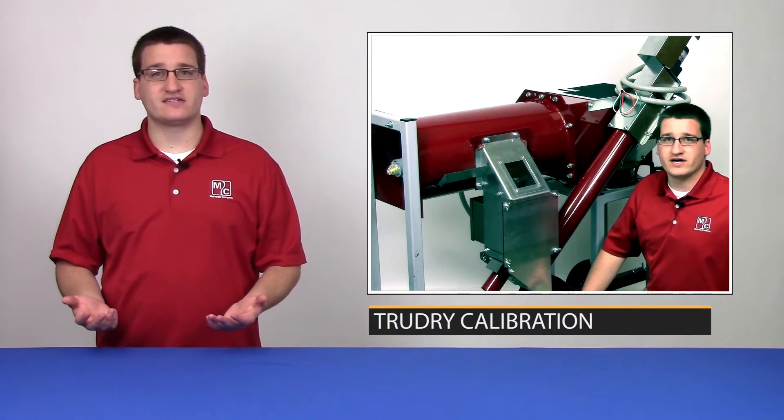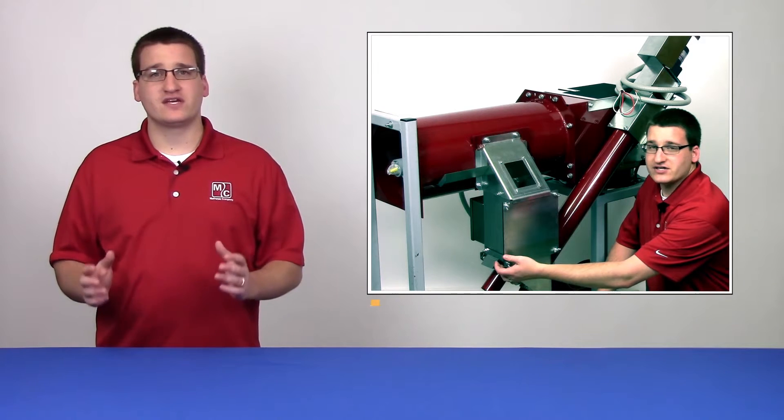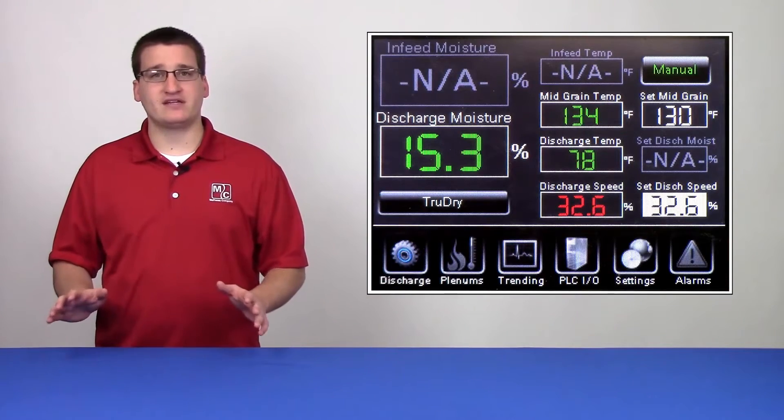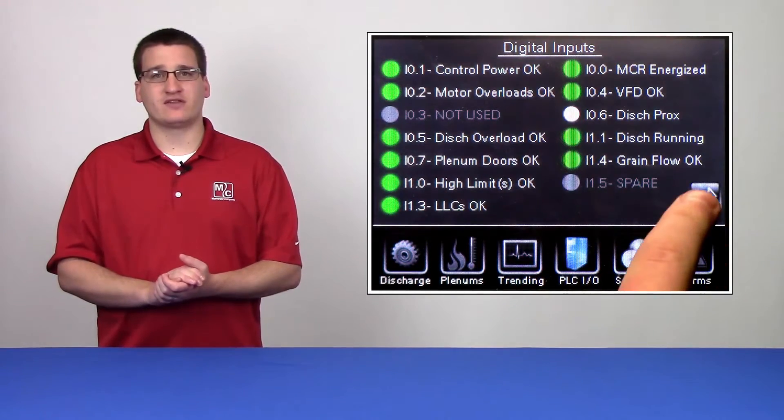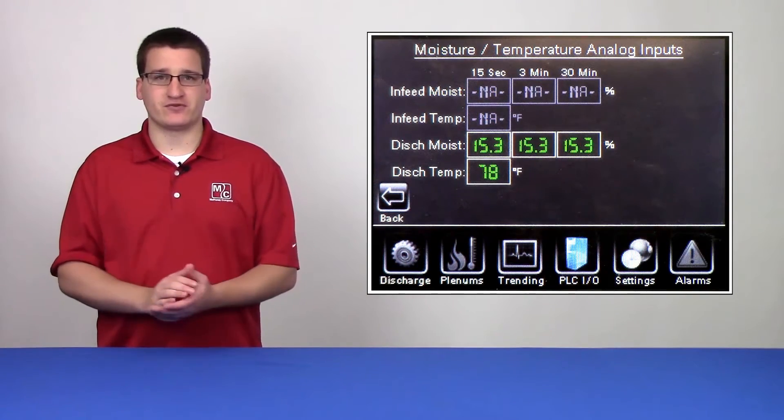Now that we've seen how to take a sample, let's walk through the calibration process. First, you'll have to go out to the dryer and take a good sample. Immediately following the sample, go over to your HMI, tap the PLCIO button on the ribbon, and hit the next button until you see moisture and temperature readings.